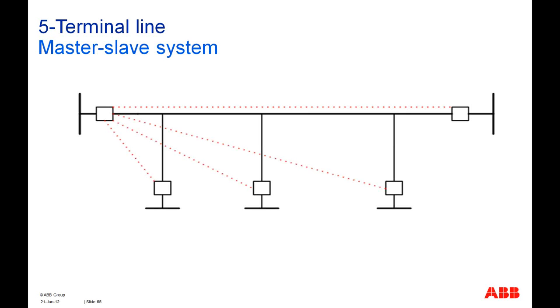So both of these master-master as well as master-slave systems are used, and have their own advantages and disadvantages. In a master-master system, you have more redundancy, whereas in a master-slave system, if any communication link breaks, then the line differential protection scheme will cease to exist. But in a master-master system, the amount of fiber optic links and fiber optic cabling is much more than that of a master-slave system.